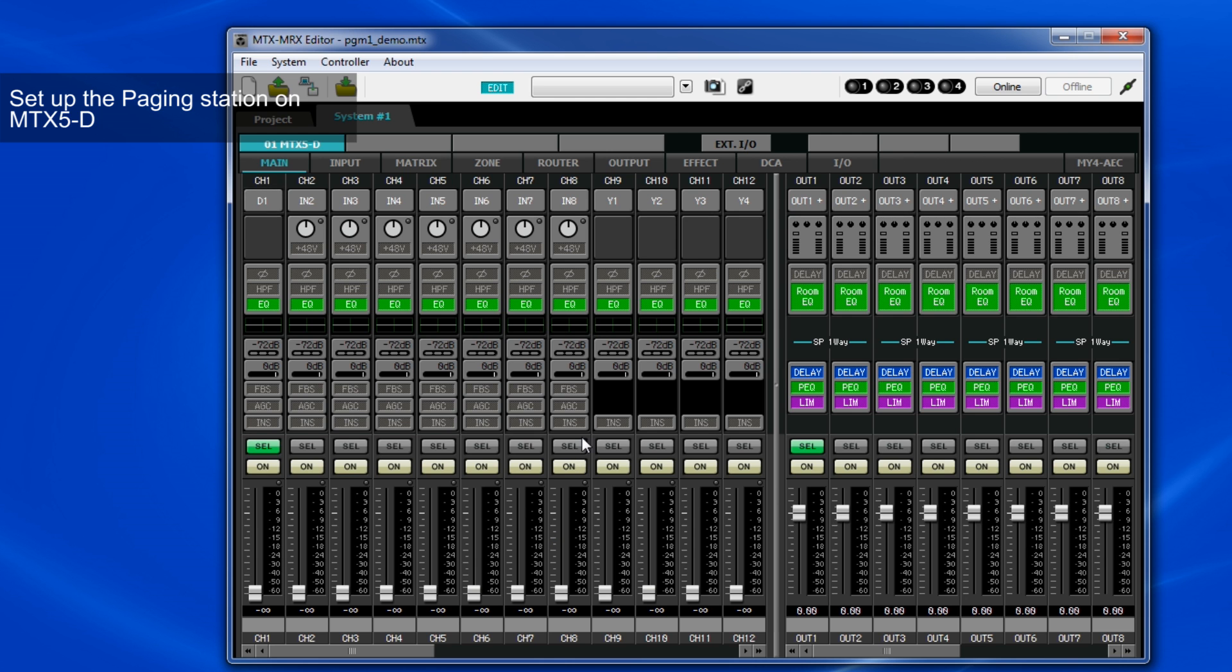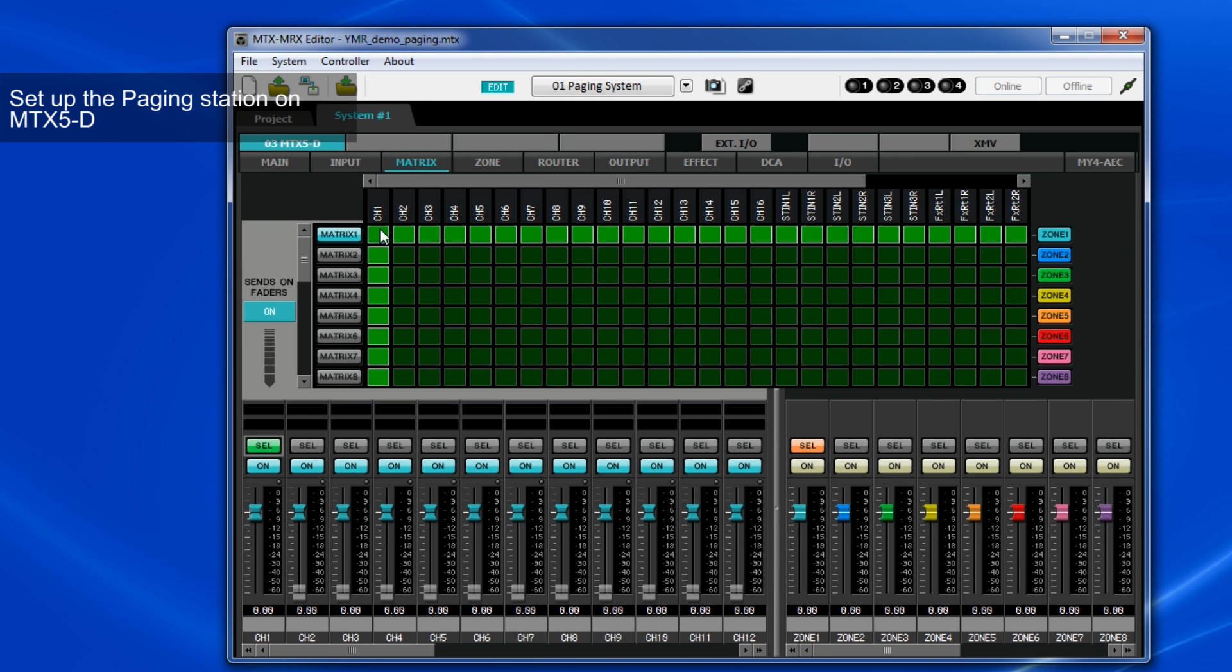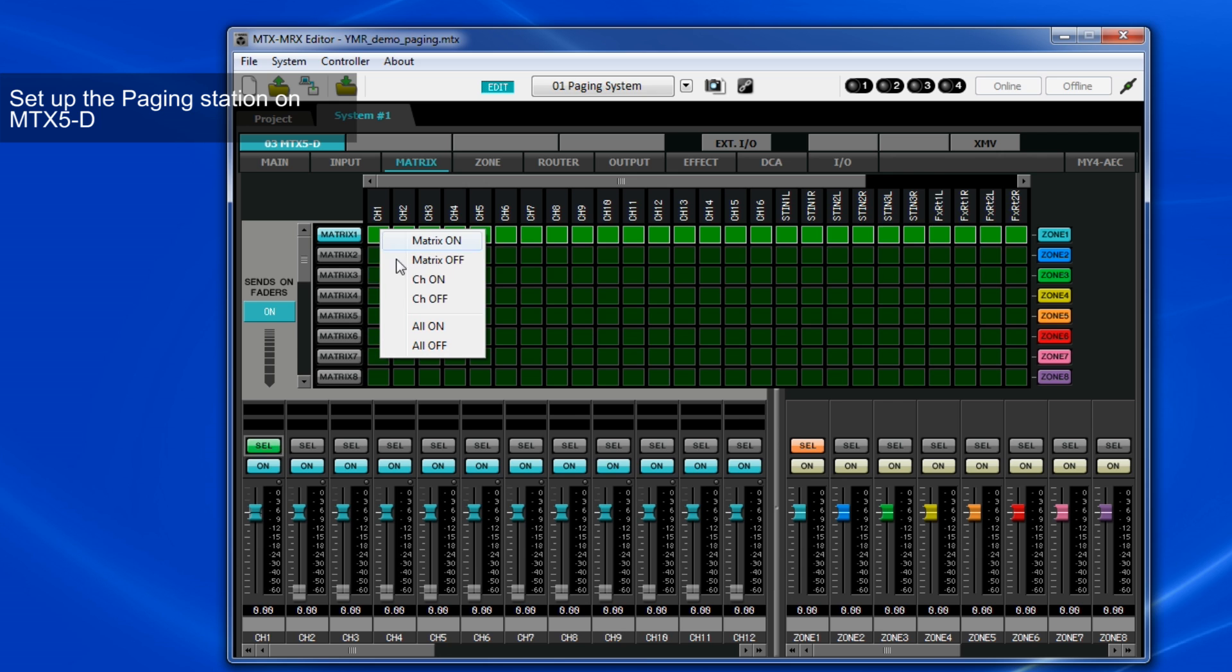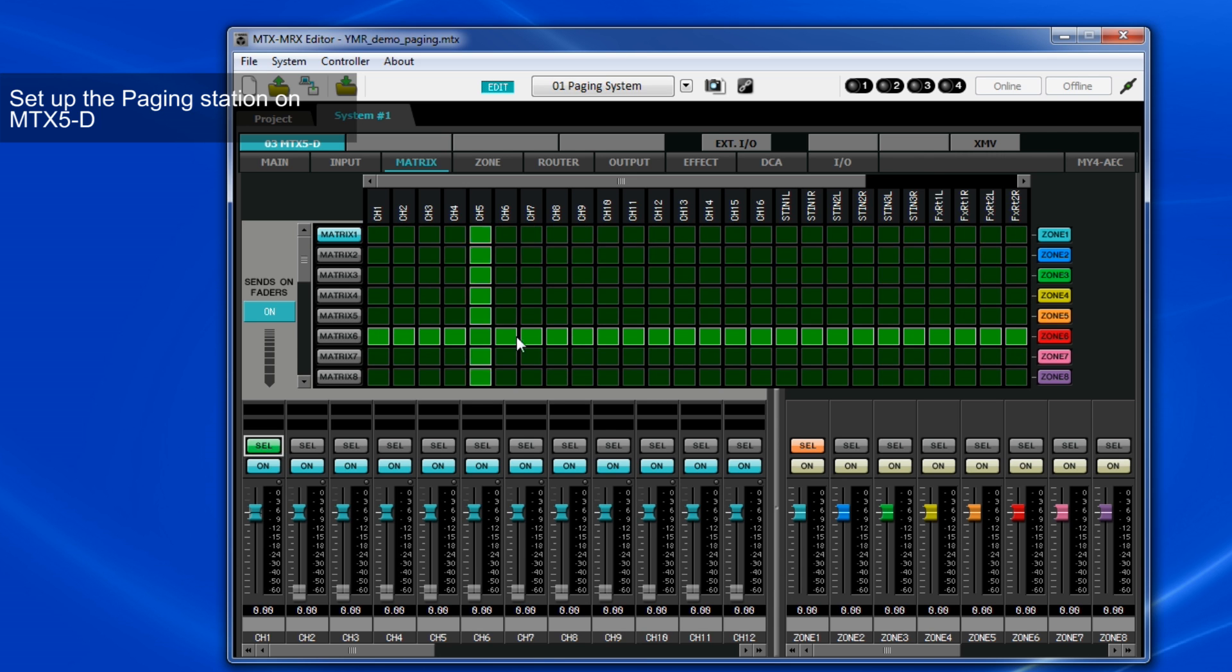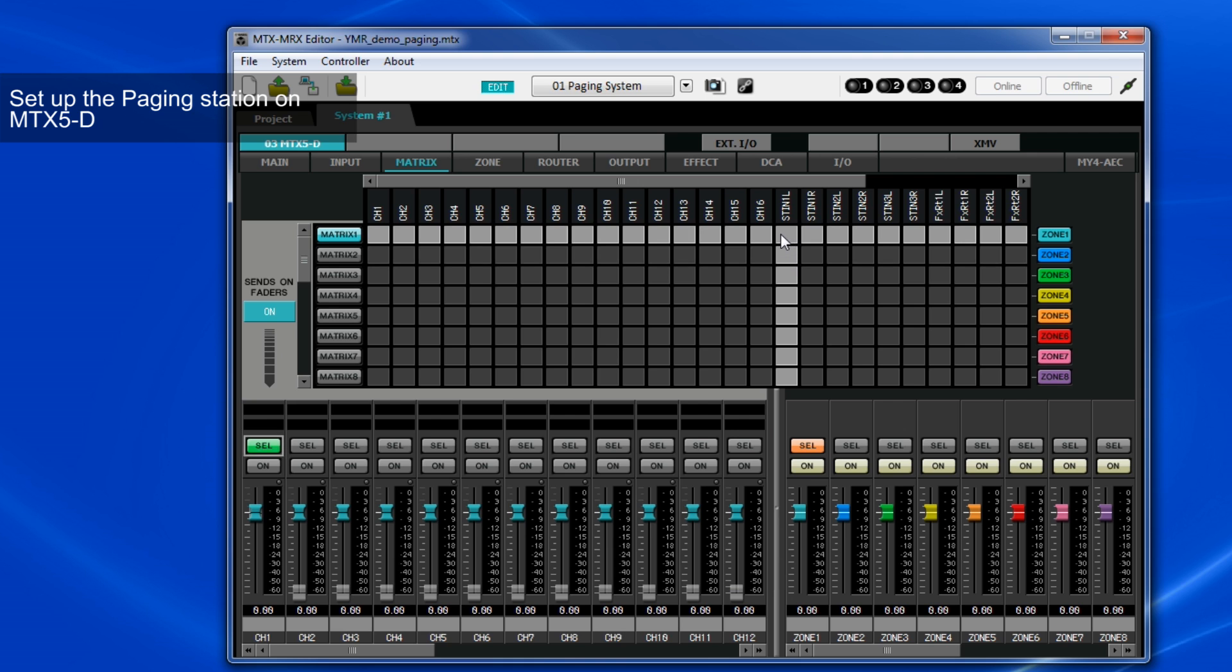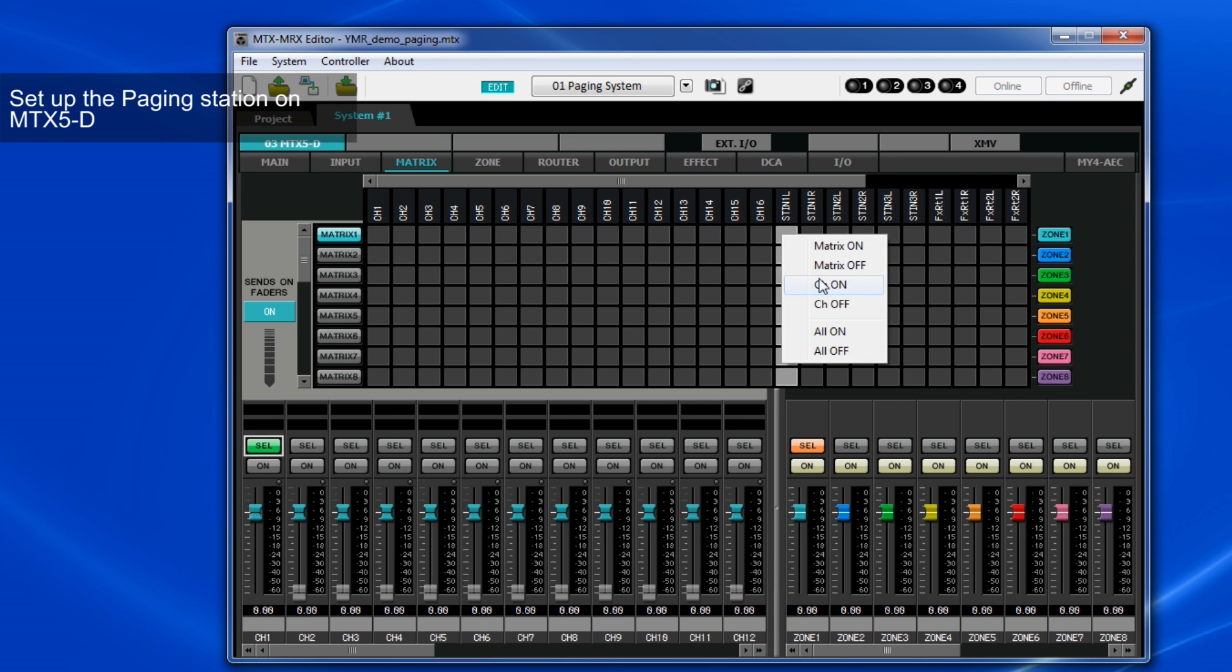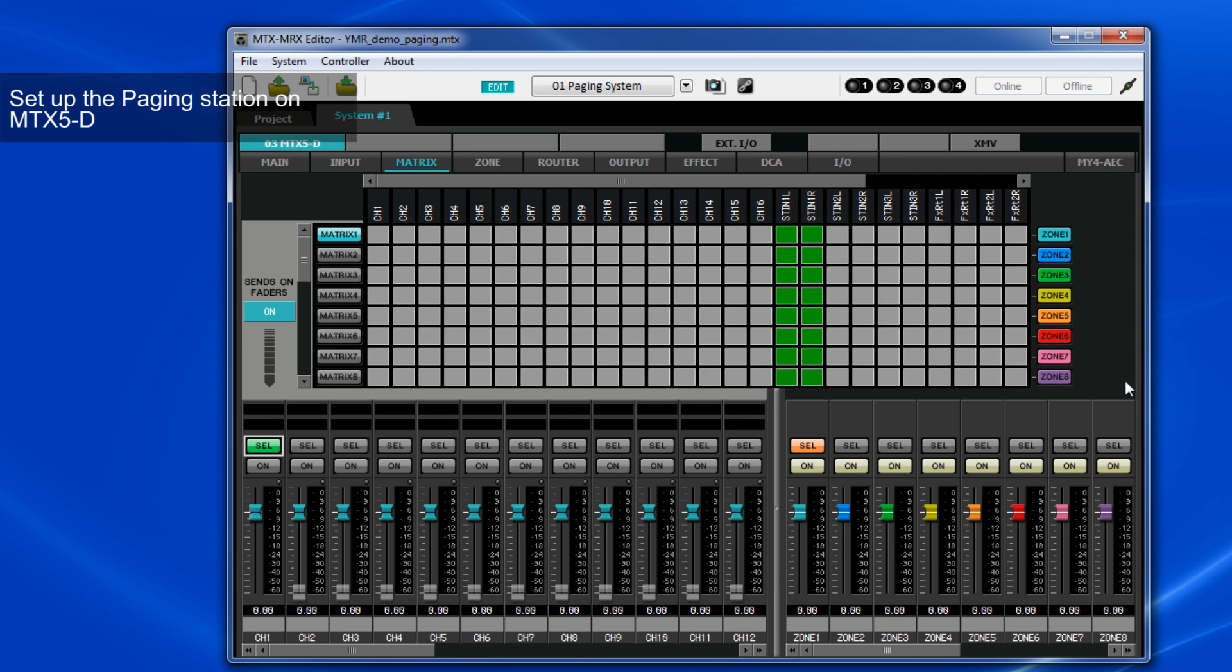Next, open the Matrix page. As all input channels are patched to all zones by default, it's necessary to switch off the patching of the channel for the Paging Mic. Please note that we're using Stereo-In 1 for background music here, so make sure that Stereo-In 1 is patched to all zones.